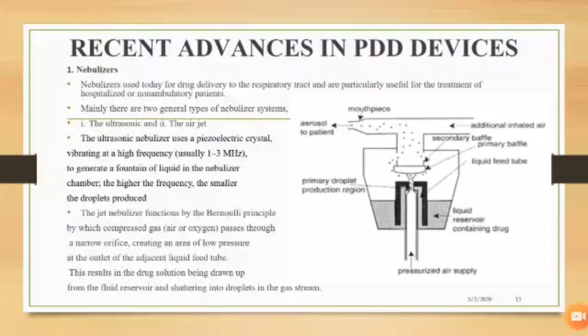In a jet nebulizer, compressed gas passes through a narrow orifice, creating an area of low pressure, so the pressure over the tube decreases. As a result, the formulation is drawn into the gas stream and nebulization is achieved due to the higher shear rate in the jet stream. Let's see some of its advantages.